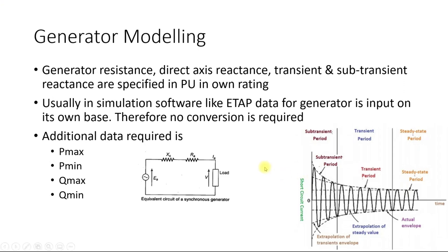Whenever you have to model a generator, you need to know all three of these reactances. For steady state analysis or load flow analysis, we only require the synchronous reactance or the direct axis reactance. But if you are performing short circuit analysis, we will usually consider sub-transient reactance, because during the sub-transient period the reactance is the lowest and the short circuit current will be highest. In simulation software like ETAP, generator data is input on its own base, so no conversion is required.